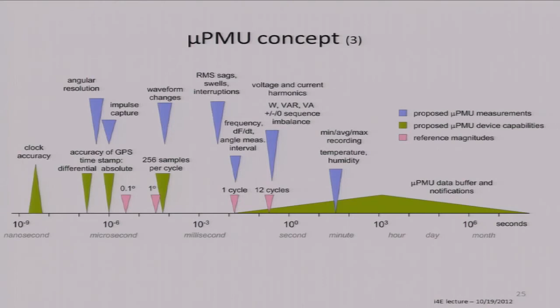For those of you who are interested in the instrumentation, there's a really interesting challenge, that when you're doing power quality disturbance measurements, it's really important to get 2 to the n samples per time interval, typically a cycle or 12 cycles, so that you can do all sorts of harmonic analyses without any kind of bleeding over the edges when you do a Fourier transform. If you have 2 to the n samples in the time interval, that's very, very useful for doing the analysis. But the frequency changes all the time. So your frequency of your sampling algorithm has to track the frequency of the grid so that you always get, let's say, 512 samples per cycle. You have to be tweaking it up and down constantly.